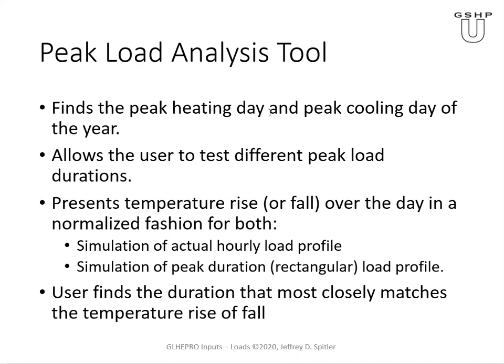But what the tool does is it takes 8,760, in other words, one year's worth of hourly loads for heating and cooling. And from there, it finds the peak heating day and the peak cooling day. It lets the user then examine the testing of different peak load durations in an attempt to establish how long the peak duration should be.